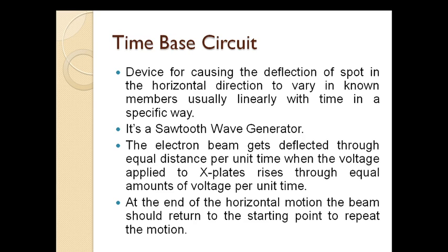The signal that you want to analyze, the signal that you want to display on the screen of CRO, is always given to the vertical deflecting plates, that is the Y plates, which creates a vertical deflection. To the X plates we give the sawtooth wave from the time base circuit, and the sawtooth wave on the horizontal plates and the signal to be displayed on the vertical plates are combined, and they create the signal you have given to the vertical plates for analysis on the screen of CRO.